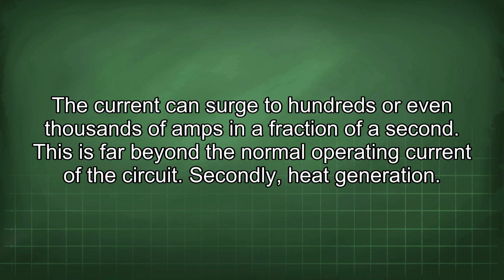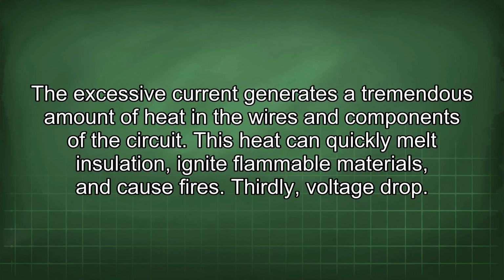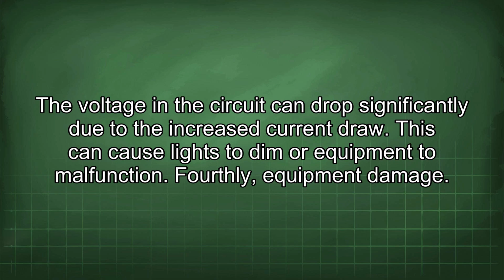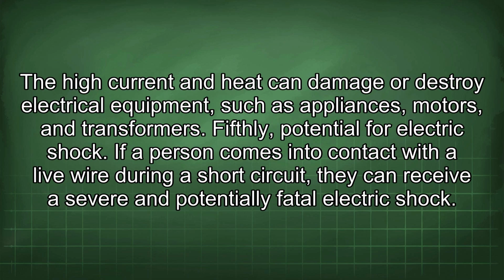Secondly, heat generation. The excessive current generates a tremendous amount of heat in the wires and components of the circuit. This heat can quickly melt insulation, ignite flammable materials, and cause fires. Thirdly, voltage drop. The voltage in the circuit can drop significantly due to the increased current draw. This can cause lights to dim or equipment to malfunction. Fourthly, equipment damage. The high current and heat can damage or destroy electrical equipment such as appliances, motors, and transformers.